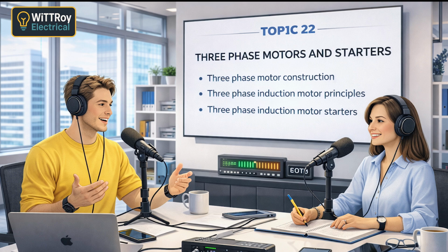And primary resistance starters? Those insert resistors in series with each phase during start. They reduce voltage but waste energy as heat. So not very efficient. Correct. They're rarely used today, mostly in older installations. And electronic starters? Also called soft starters. They use semiconductor devices to gradually increase voltage. So very smooth starting. Exactly. They reduce mechanical stress and electrical disturbance, and the start parameters can be adjusted. Any disadvantages? Cost and some harmonic distortion. Where are they commonly used? Pumps, conveyors, HVAC systems, and modern industrial motors.